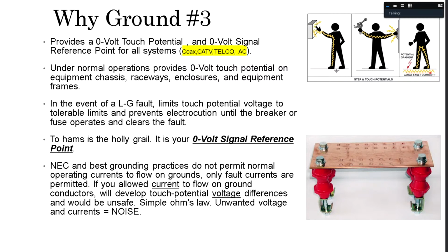Okay, but NEC and best grounding practices do not permit normal operating currents to flow on grounds. Only fault currents are permitted. If you allow current to flow on your ground conductors, it's going to develop voltage on those ground conductors. And it's just as simple as Ohm's law. So any unwanted voltage and currents are noise.